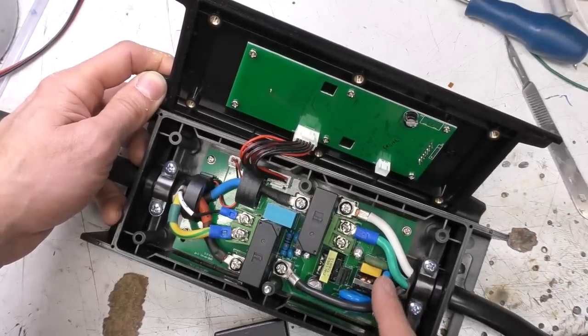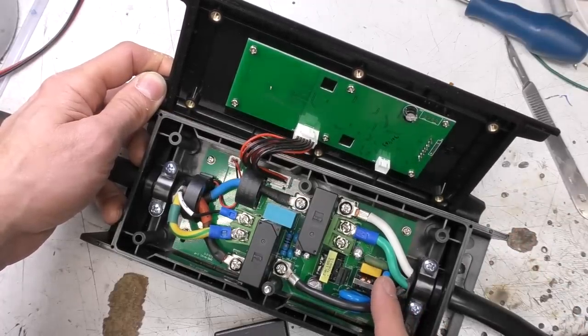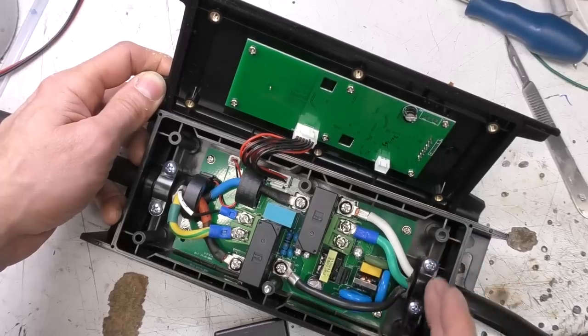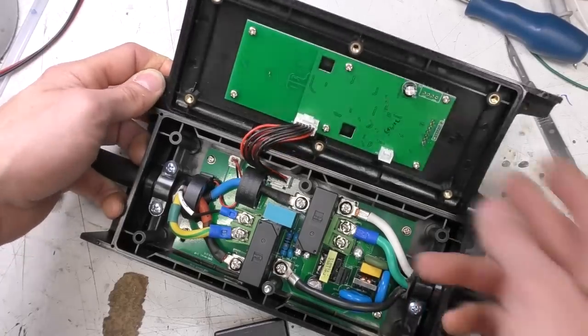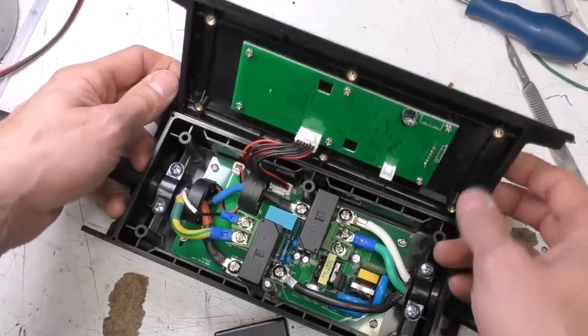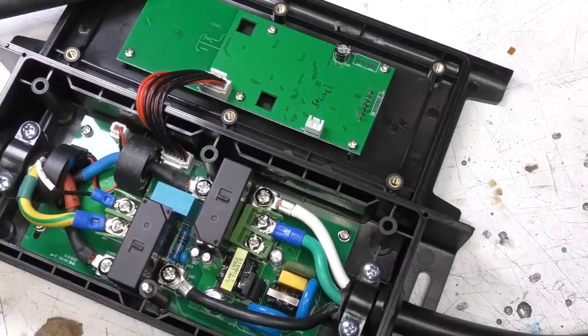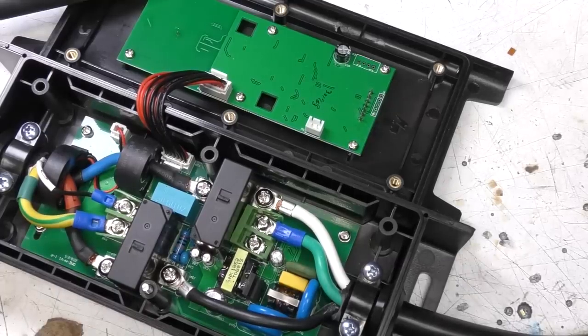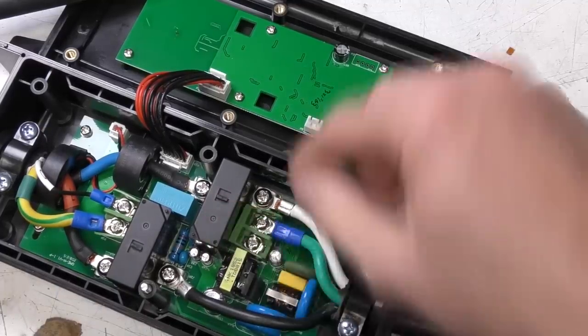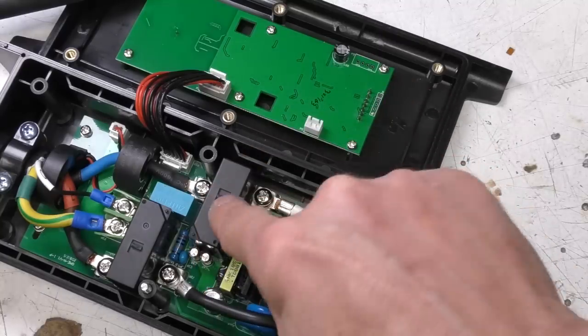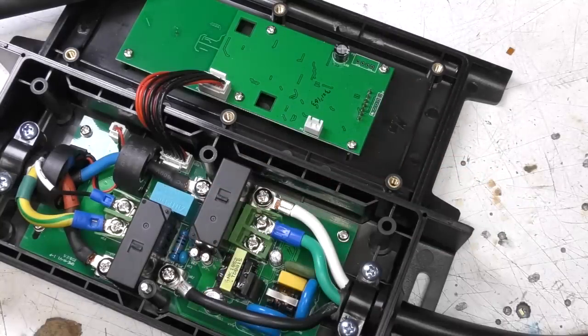You actually had to chop the crimps off and recrimp them, and that was because the space was so cramped, that was really tricky. So this one on first look is certainly a lot easier to get apart. Now this uses the same 50 amp Hongfa latching relays. The difference is this uses a version that's got a manual operation and indication tab on it. So if you turn them on, you can actually see the tabs flip.